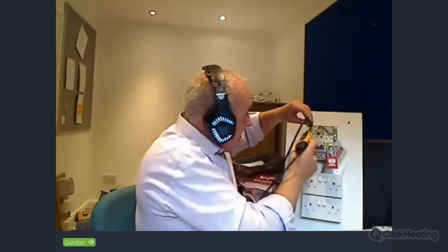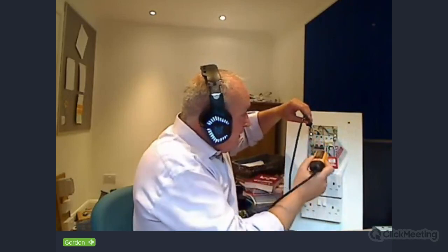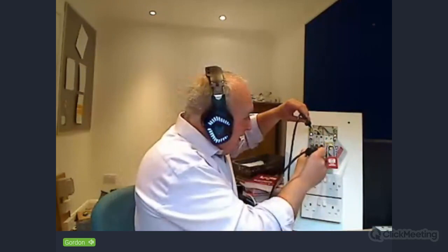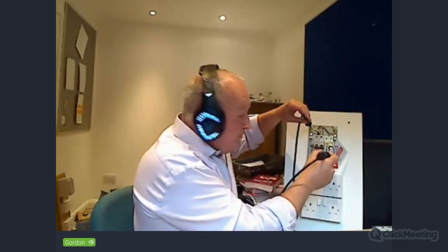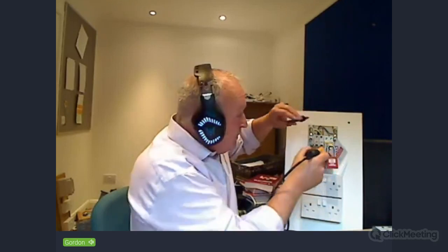Then the final test is between earth and live - again 0 volts first, so we now know this is dead against live, and that's 0 volts as well. So we've done the 3-point test and that is completely isolated. What's the last bit we need to do? Correct - we need to retest the voltage indicator on the proving unit.